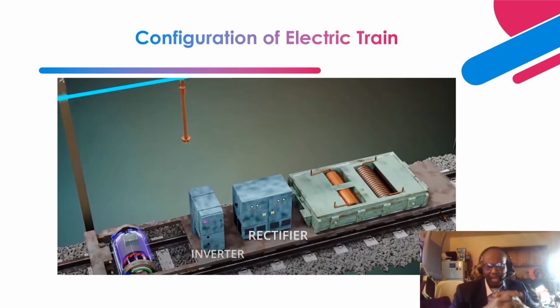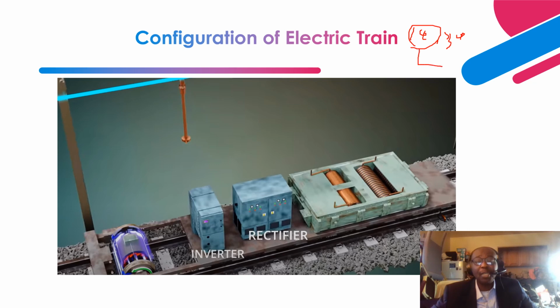So remember I indicated that sometimes you have a three-phase and a single-phase arrangement. It is much more efficient, reliable, and cost-effective to utilize the single-phase arrangement compared to a three-phase arrangement, and I showed you how the three-phase arrangement looks. So if you choose to utilize the single-phase arrangement, you have to convert it to a three-phase arrangement to provide a three-phase voltage to the motor, since the motor requires a three-phase voltage.